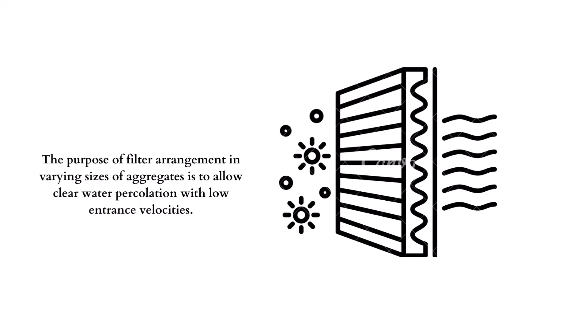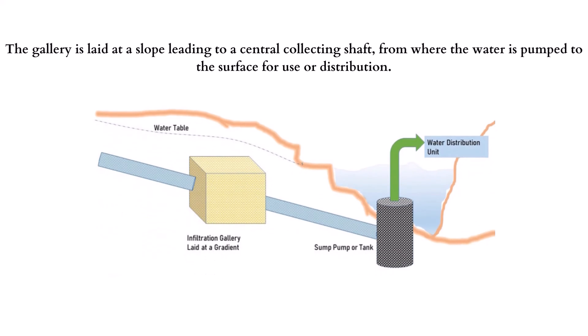The filter medium is typically made of gravel, but it can be improved based on available technologies. The purpose of the filter arrangement with varying aggregate sizes is to allow clear water percolation with low entrance velocities. The gallery is laid at a slope leading to a central collecting shaft from which the water is pumped to the surface for use or distribution, making the gravitational flow and movement of water easier.